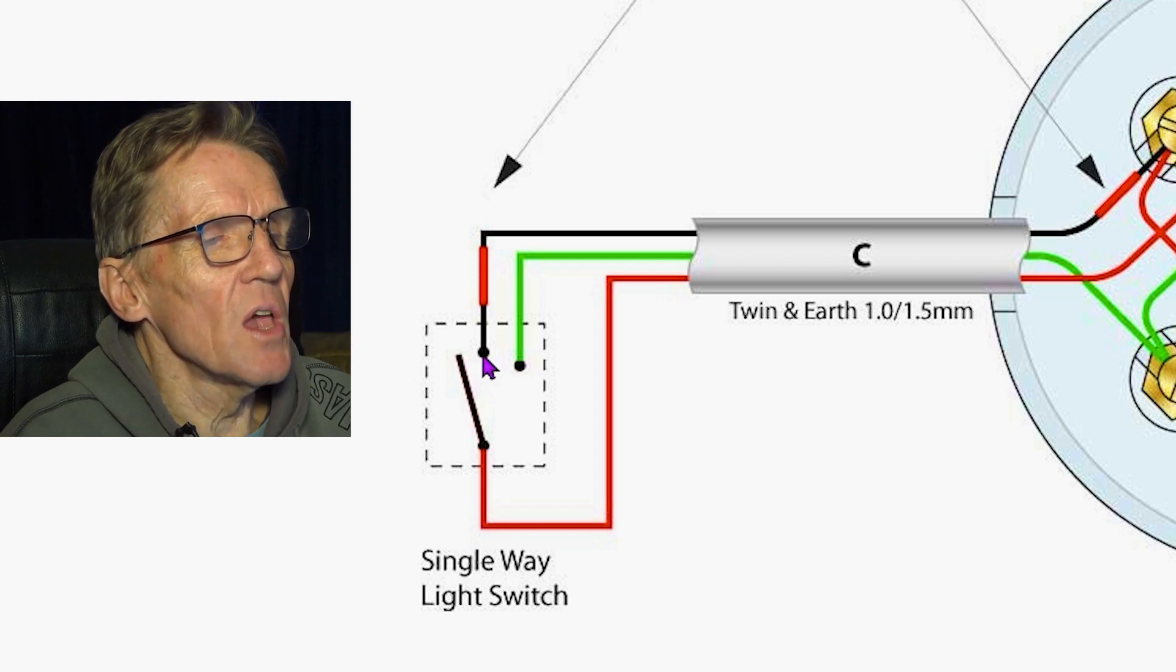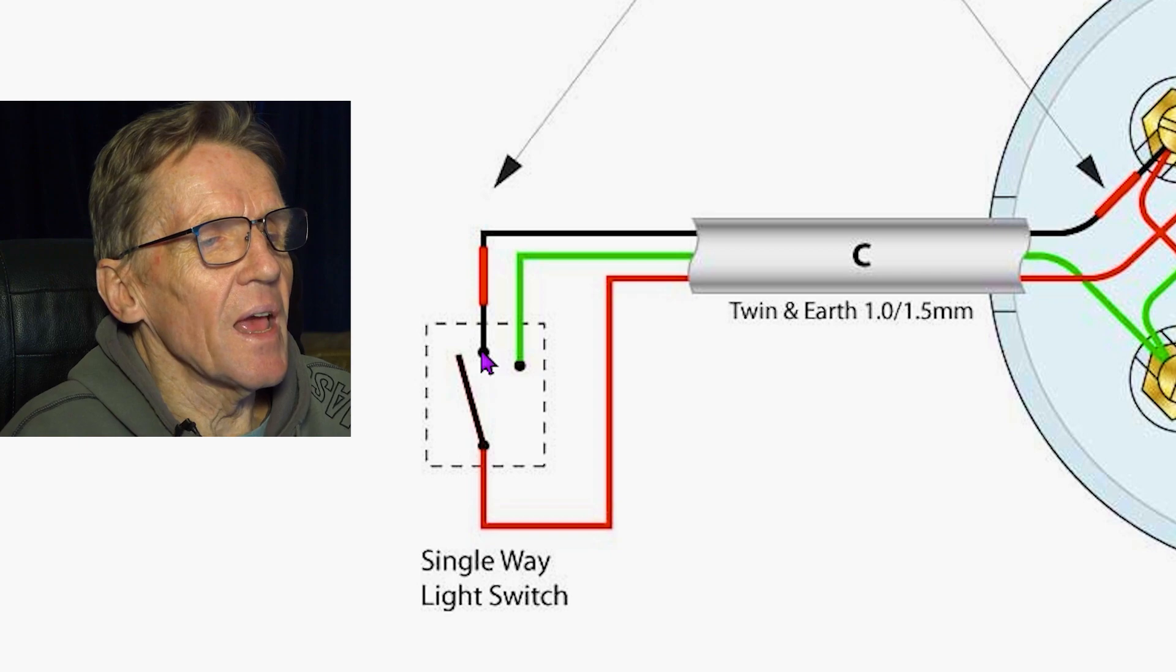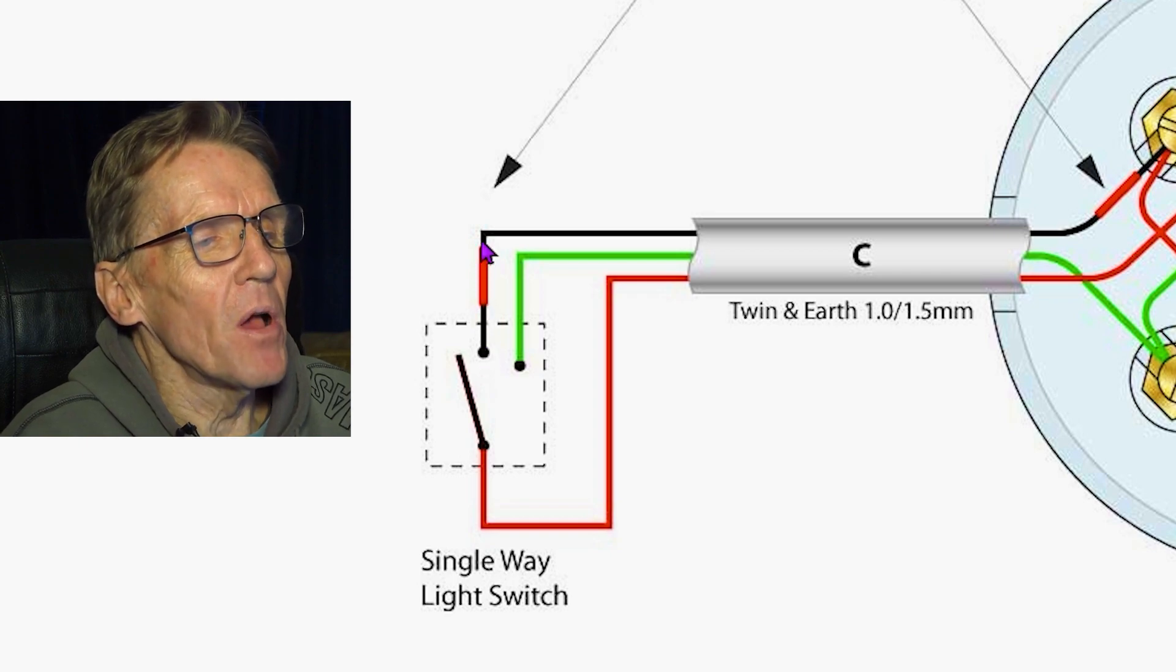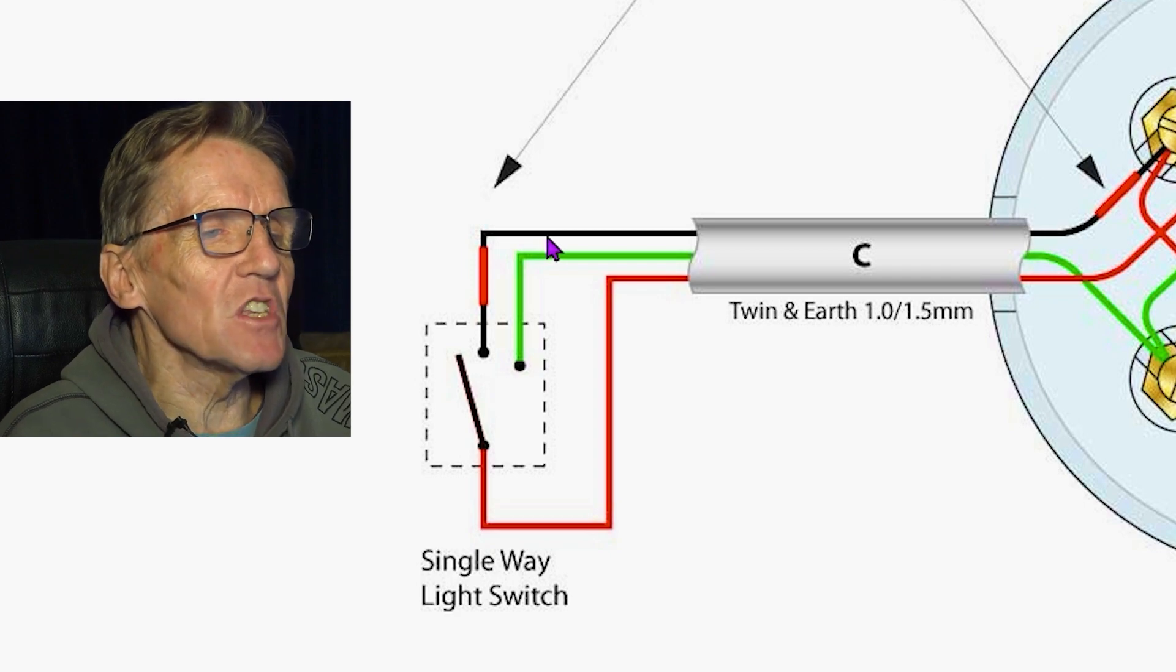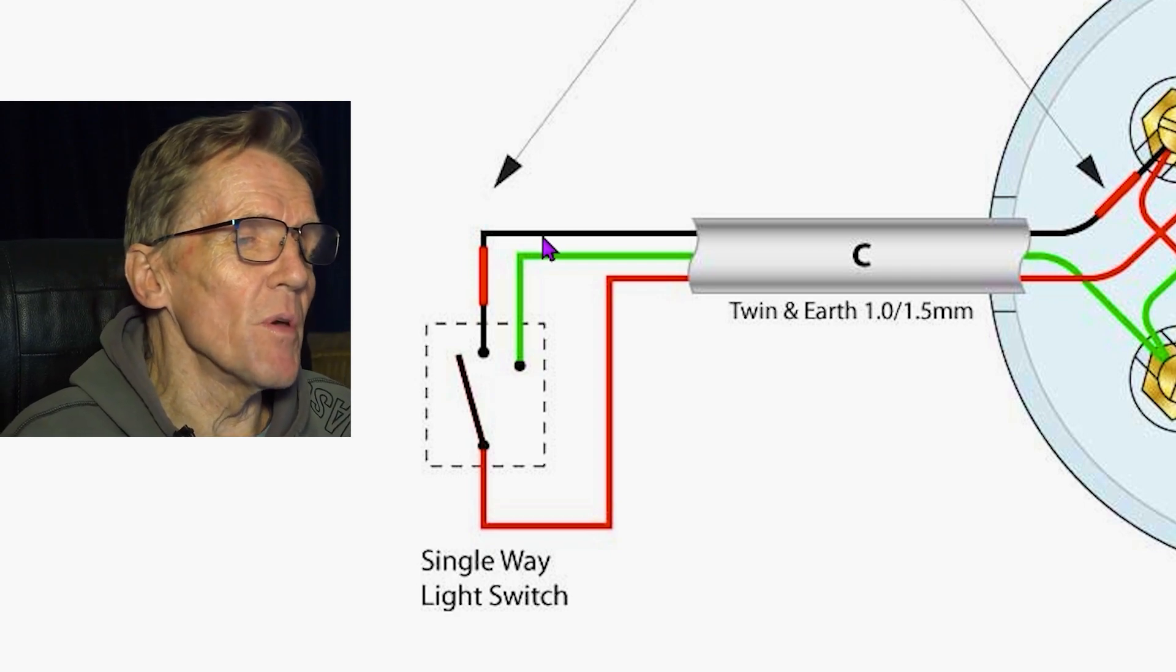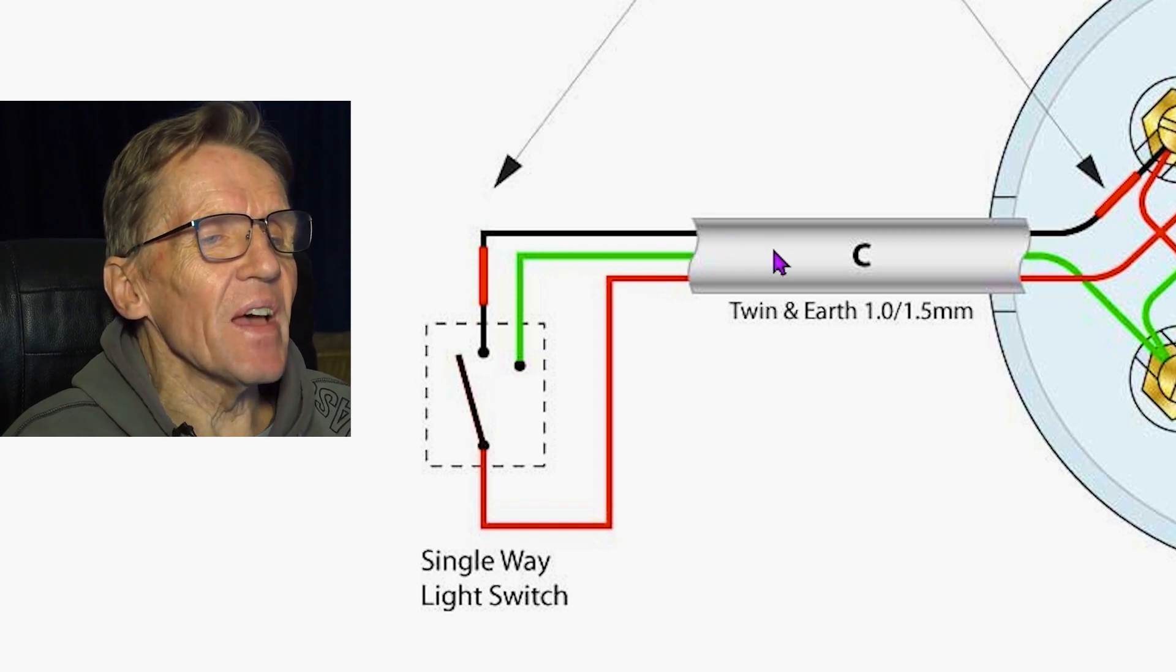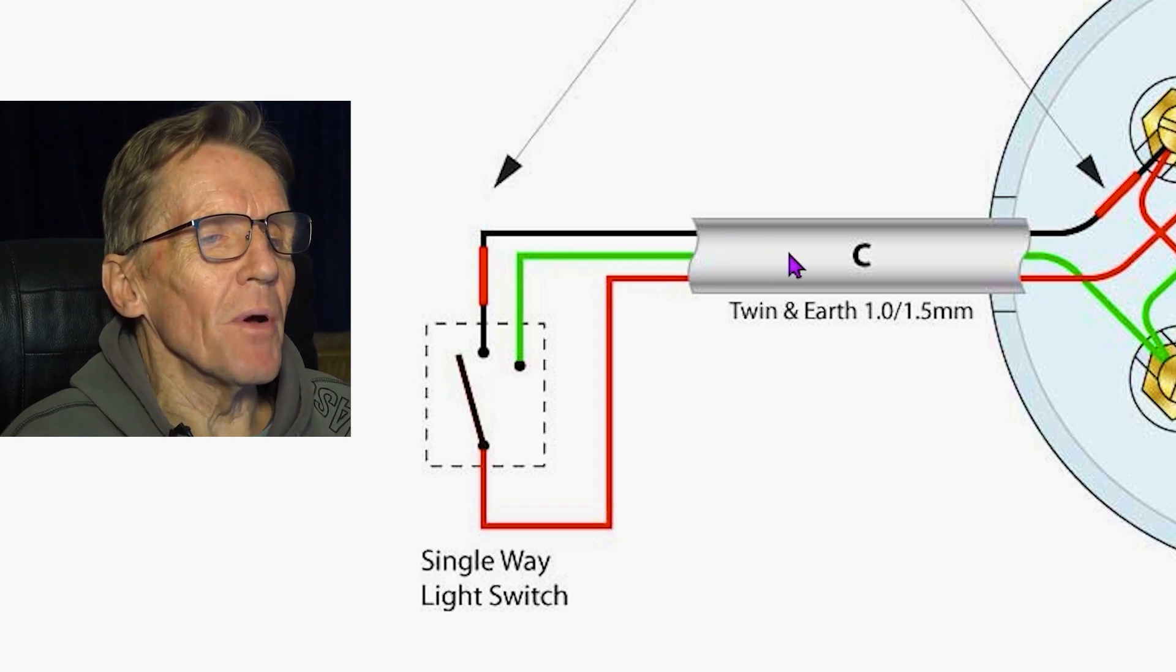When that switch goes across, it makes the circuit, and at this point we've got a live going back up on the black wire. Now the reason it's black is because the cable comes either with a brown and a blue or a black and a red as it used to be, and that's the kind of cable we're using.